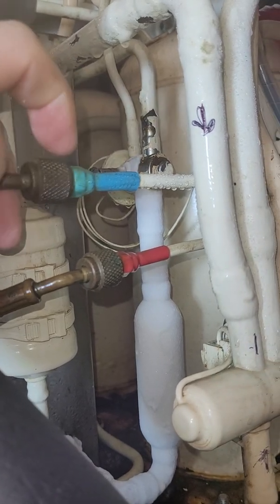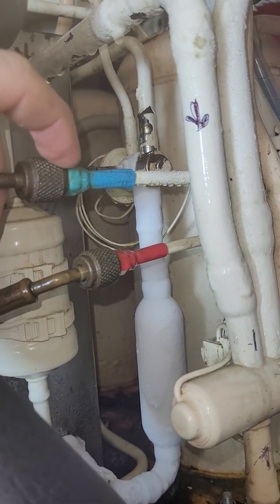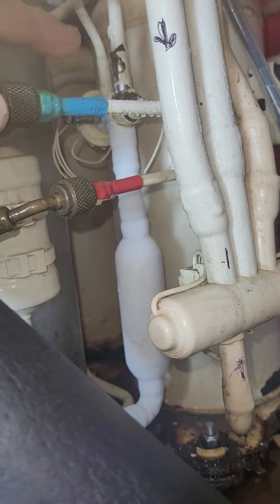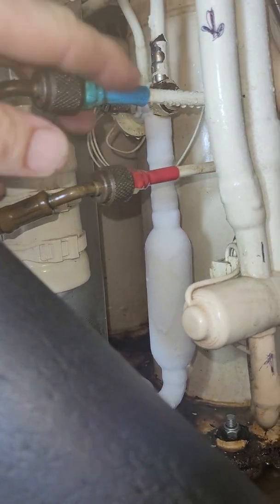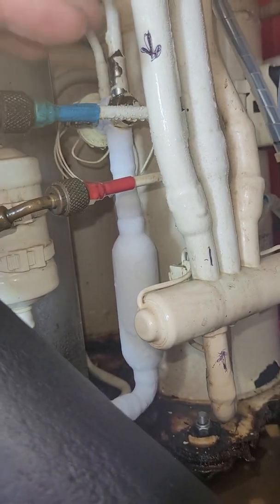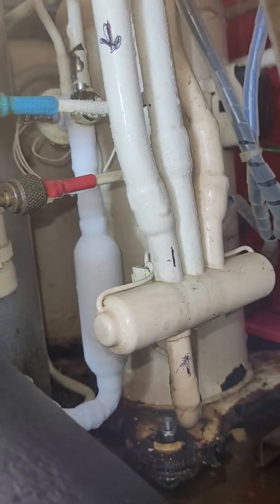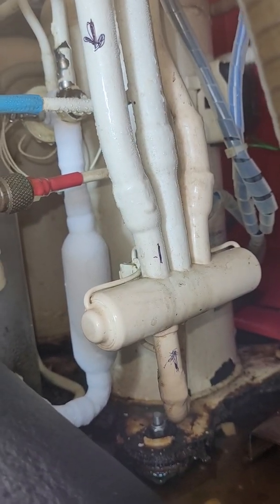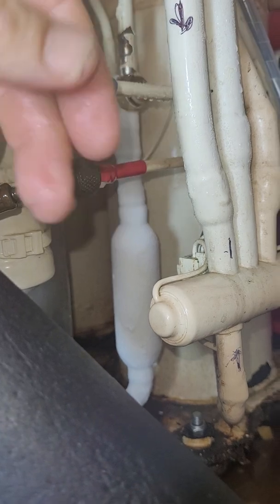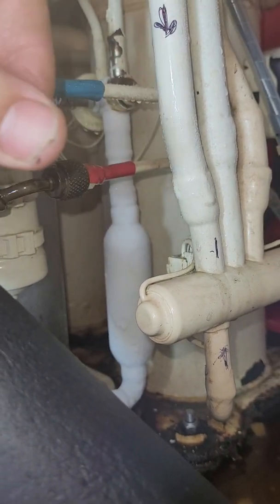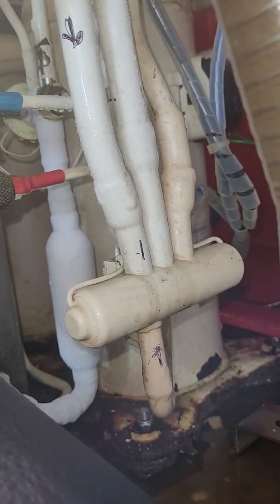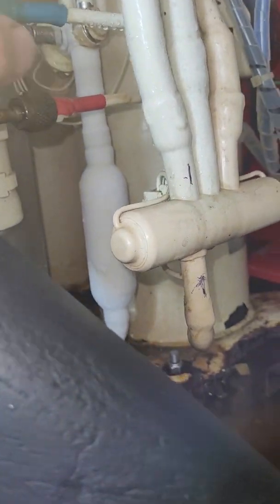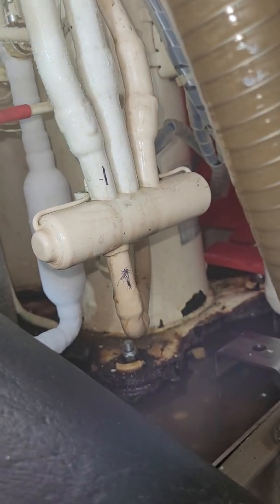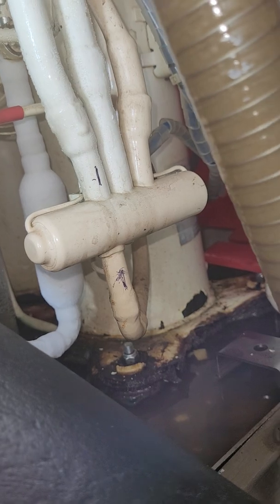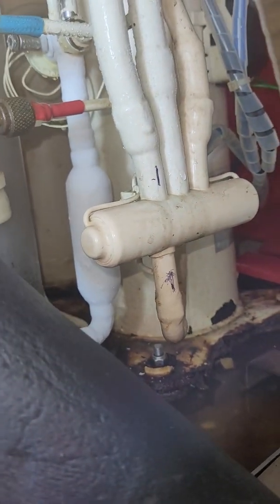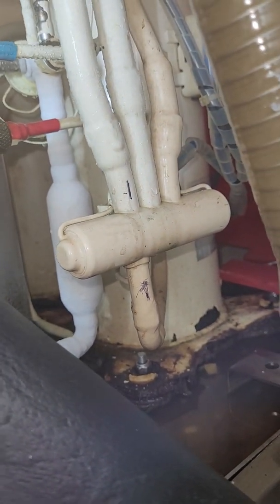You open it and you extract a little bit of the gas mixture, and in there's the gas, the refrigerant, and the oil. The oil is circulating together with the refrigerant in a kind of vaporized form. So when you extract a little bit of gas here, you will have oil on your fingers, and this is the oil that circulates in the system to lubricate the compressor. This oil and gas mixture obviously also cools the stator winding. The winding of the compressor is in the same circuit, and it gets cooled by the refrigerant.